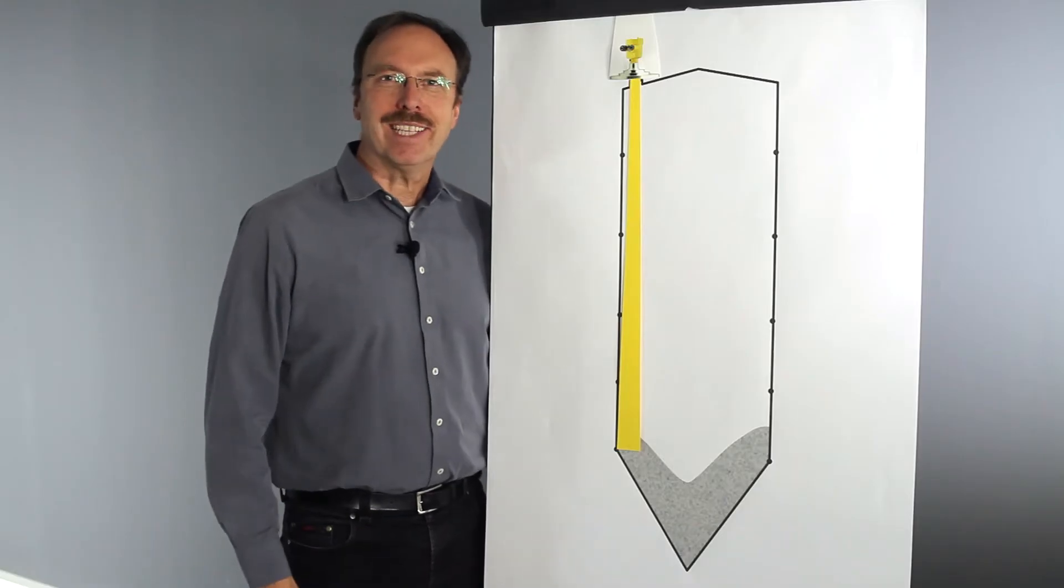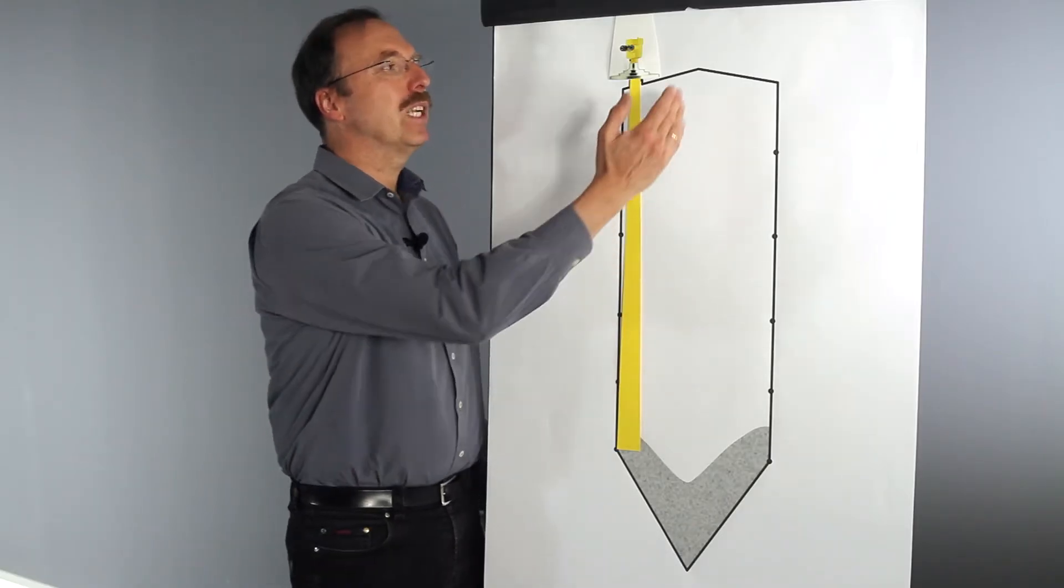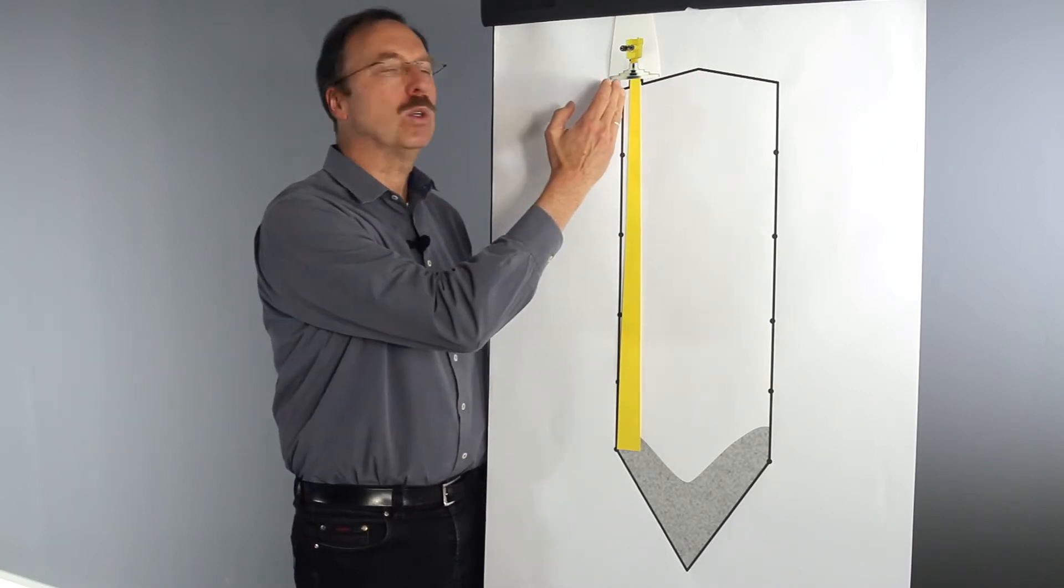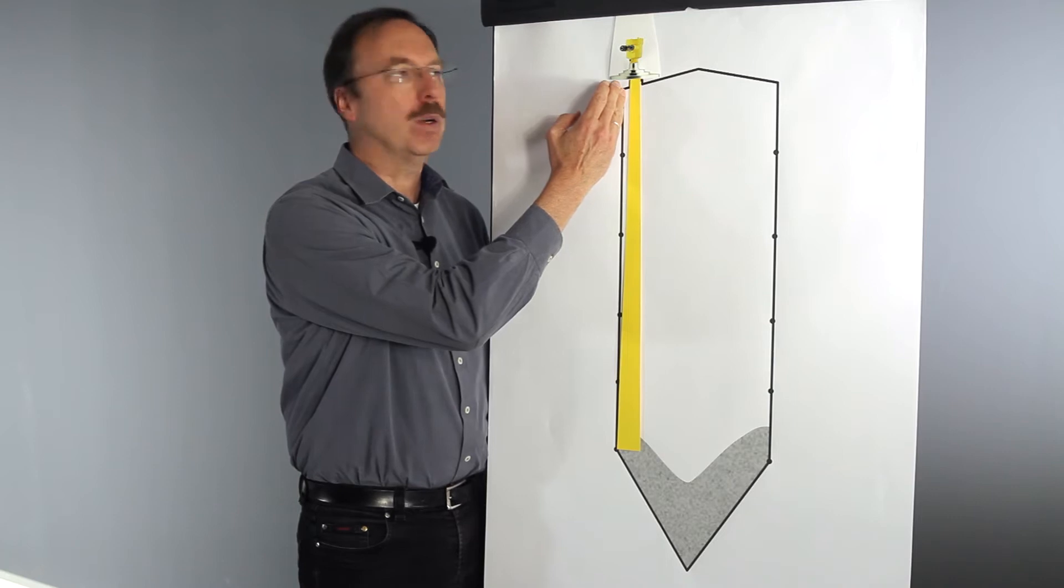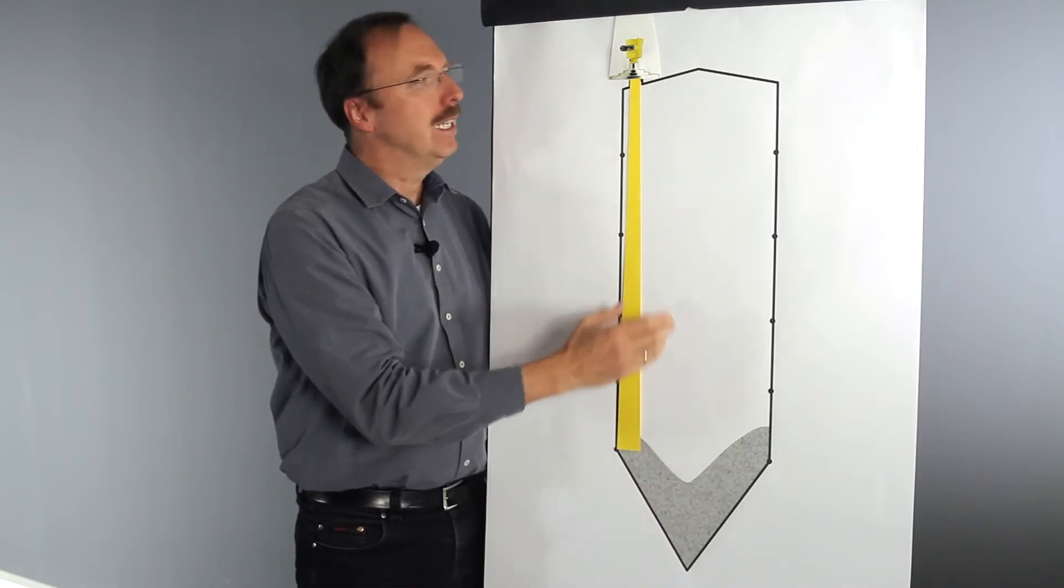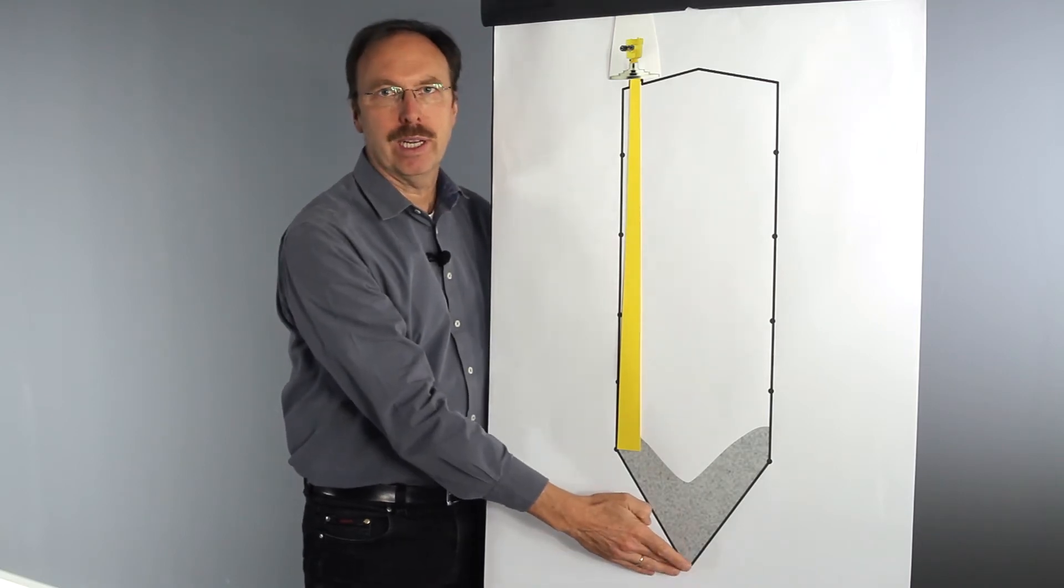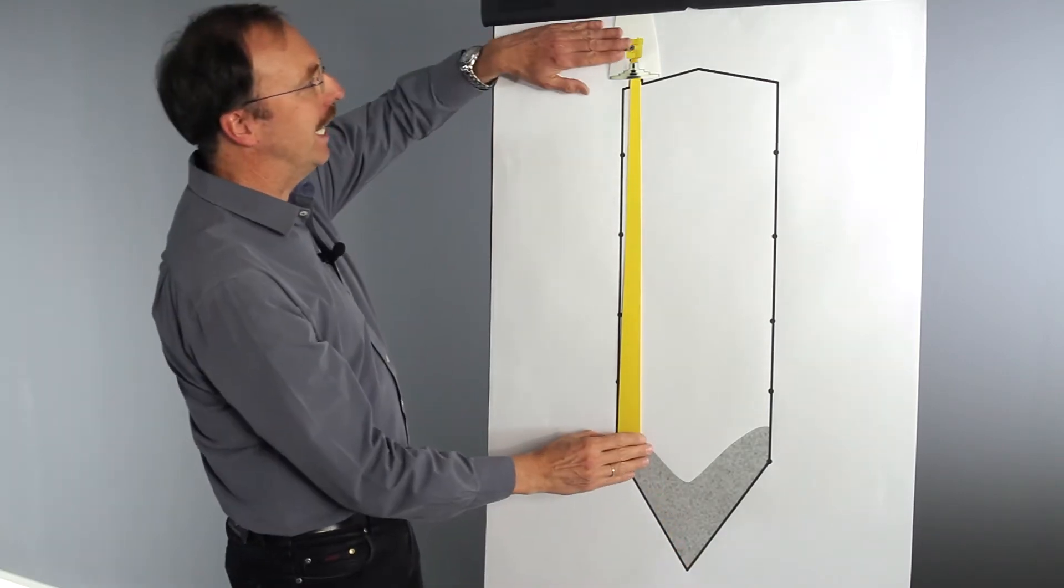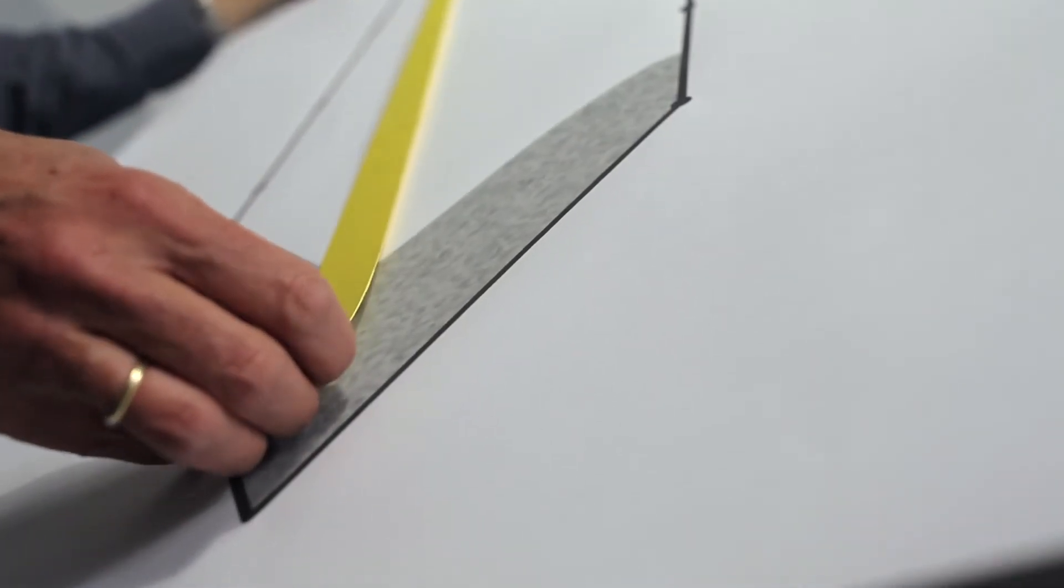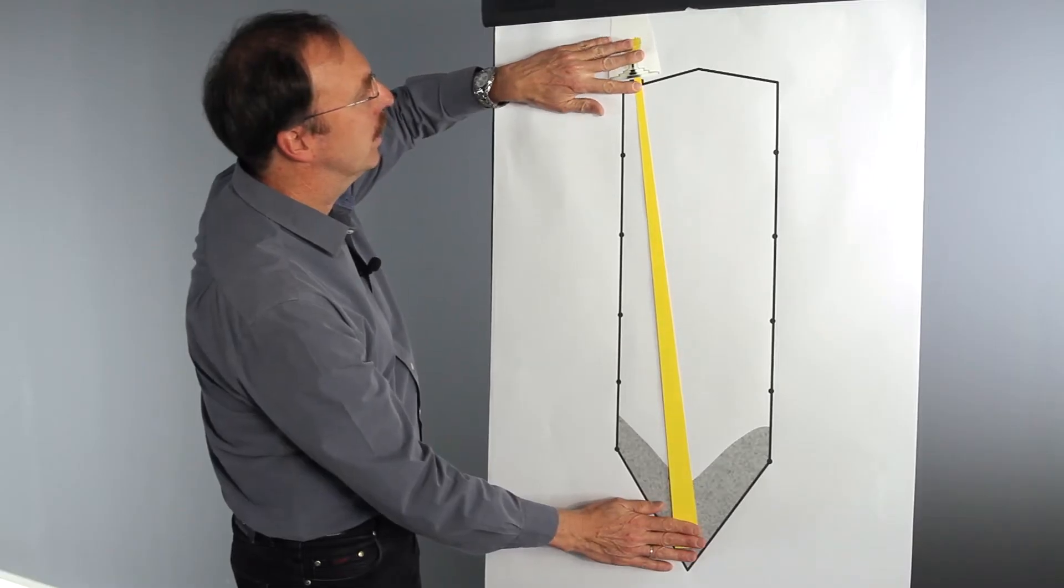To get the best measuring results, the sensor should not be mounted direct in the center of the silo. The best position is a distance between 200 and 500 mm from the wall of the silo. To get the complete volume, the sensor has to be aimed to the center of the outlet. Therefore we can aim the sensor and get the best position in this case.